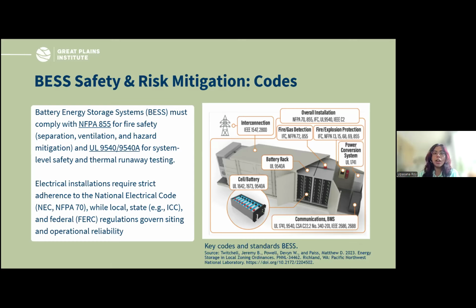Referring to that code within your ordinance will solidify your community's standards, at least for placing and mitigating BESS, because that is the industrial standard, and compliance must usually be done with industrial standards. From a system-level safety standpoint, UL 9540 is also referred to, because there's system-level safety training and testing that is part of NFPA 855 as a hazard mitigation strategy. So all of these codes are wrapped in a bundle within the BESS module, and if you refer to those codes within your planning and zoning ordinance, you're pretty much set.